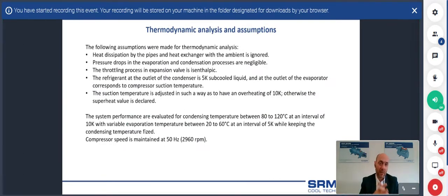Of course, we have to make some assumptions, such as the heat dissipations by the pipes and heat exchangers, because we are mapping only the compressor. So we ignore this dissipation. The pressure drops in the evaporation and condensation processes we consider as negligible. The throttling process we consider to be isenthalpic, so with the same enthalpy. We simulate the refrigerant in order to calculate the capacity, with 5K subcooled liquid, and the superheat normally is taken at 10K, so 10 degrees Kelvin. When we make the testing different from this value, normally we declare these values.